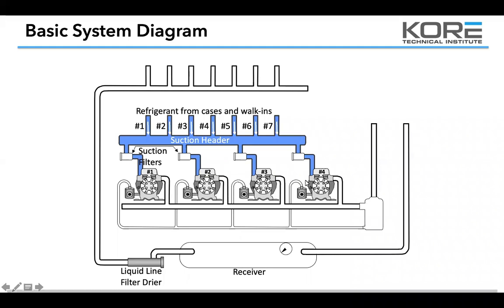Towards the end of the rack where you have larger compressors, a lot of times — especially at this time of year when you don't need as much load — you'll see that last large compressor not cycle very often. That's okay, just keep an eye on it. If it causes problems, I know some of our satellites in larger markets actually valve off that compressor for the winter, which is totally fine if you've done your load calculations.